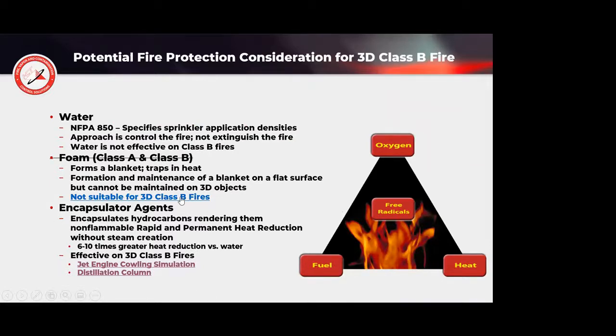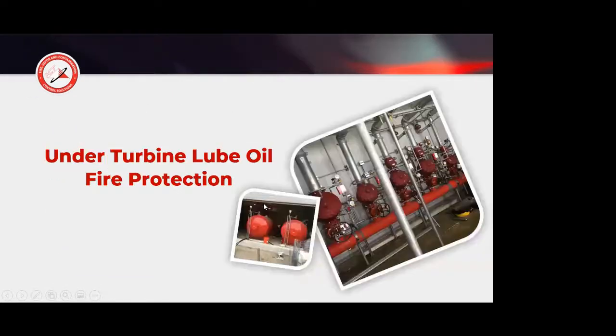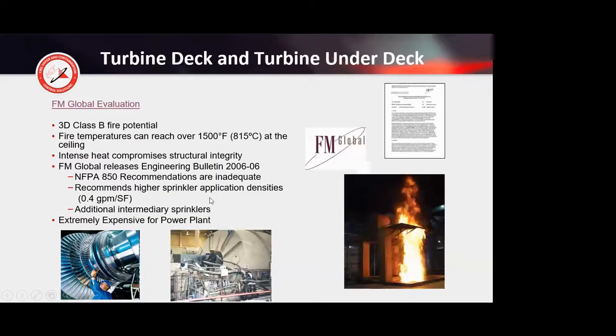The reason F500 is very capable of three-dimensional Class B fire suppression is that water isn't very good at Class B, and foam isn't suitable for Class B either. FM Global did a test and found the fire gets so hot it reached over 1,500 degrees at the ceiling, hot enough to compromise the structural integrity of the I-beams.